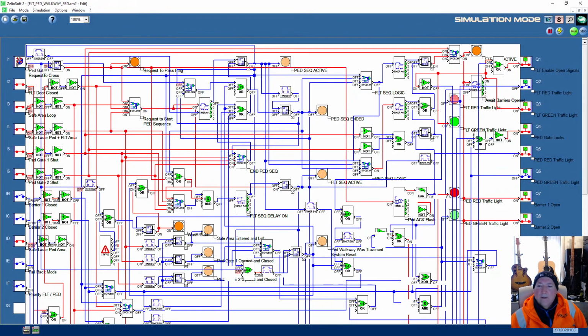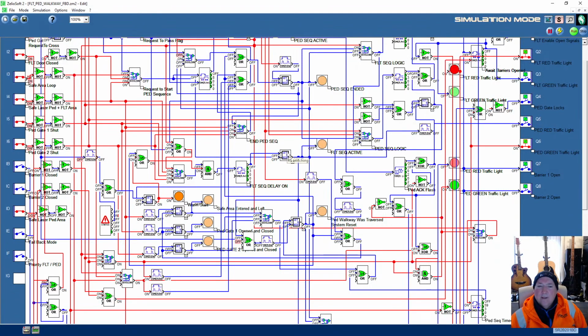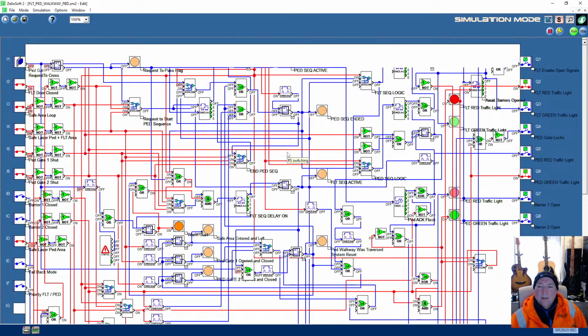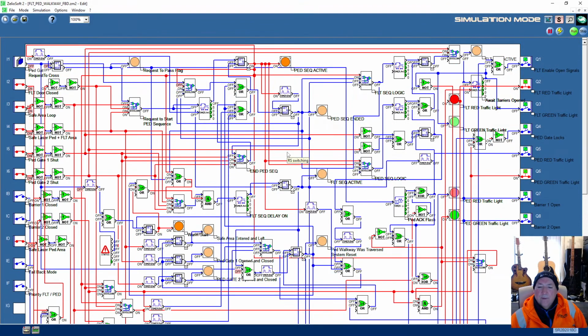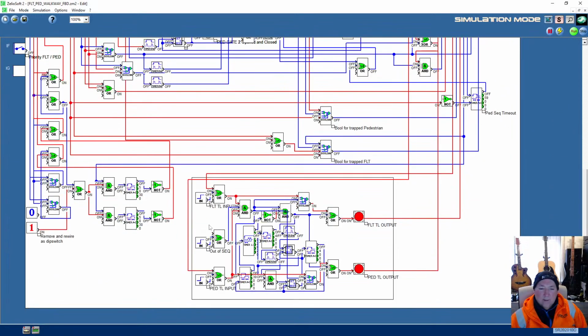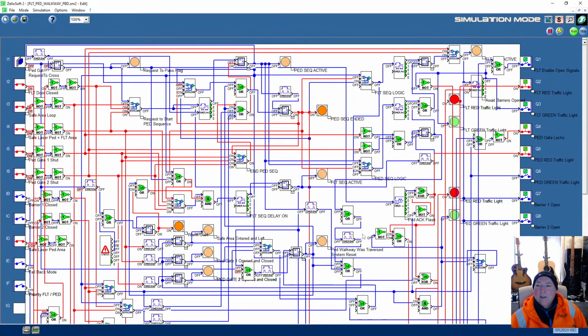We press that one. Go to red, so we've got two reds. Got a green, so we've got everything else going on as we should. We come out of sequence. Someone opens a door. So we're out of sequence, so what we do is trigger this out of sequence, and what we should get is our two flashes in out of sequence.